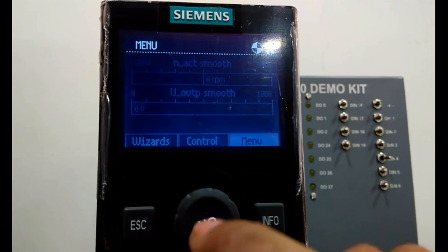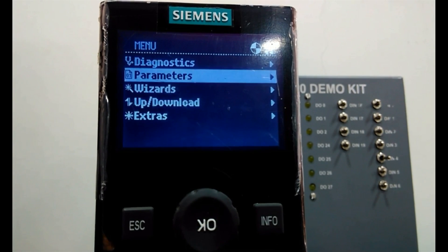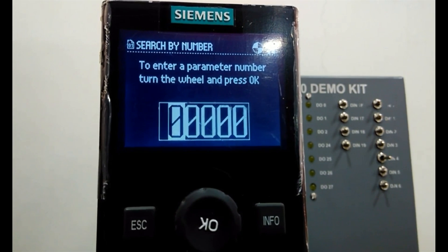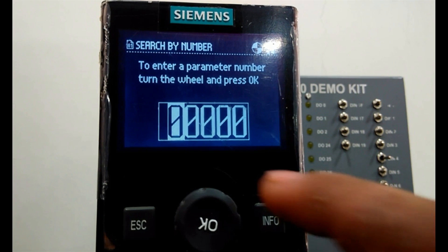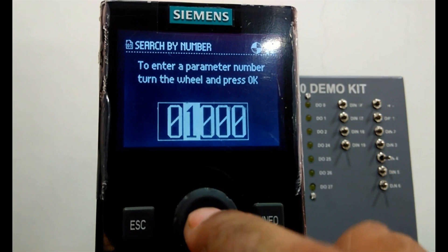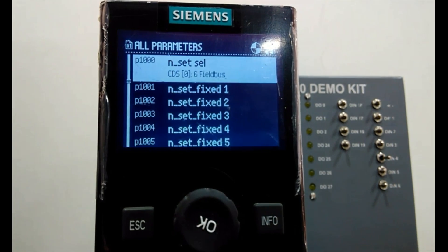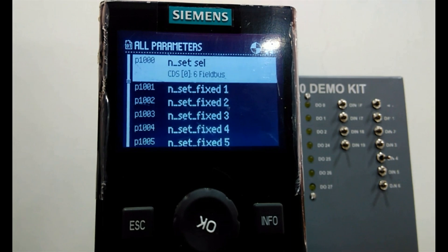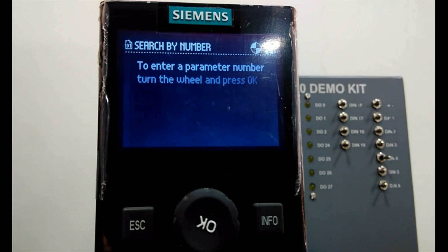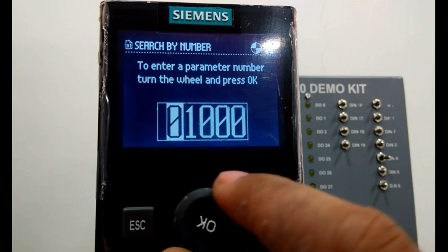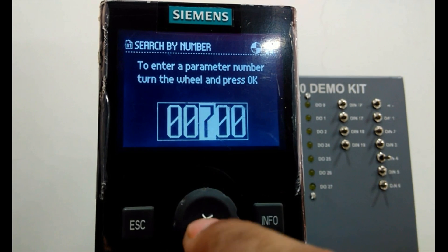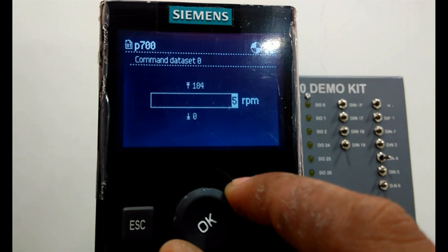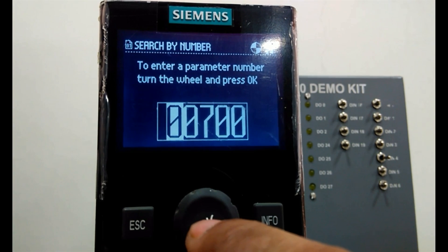First of all we will switch to the menu, from there go to Parameters and search by number. Here we will set first parameter P1000. In P1000 I will set the value 6 for the fieldbus — that will be the speed set point selection. Then escape. The second parameter we will change is P700. Here I will add the value 6, and then escape. Now successfully configured.